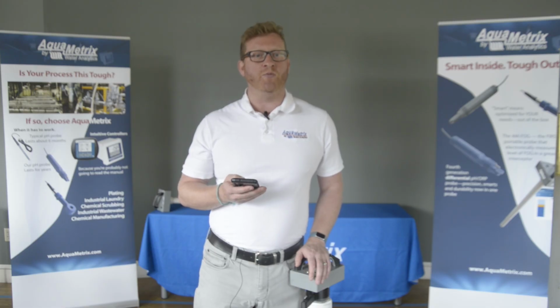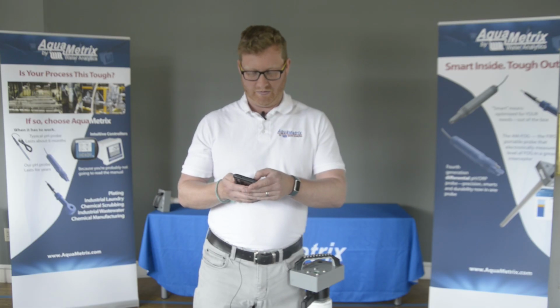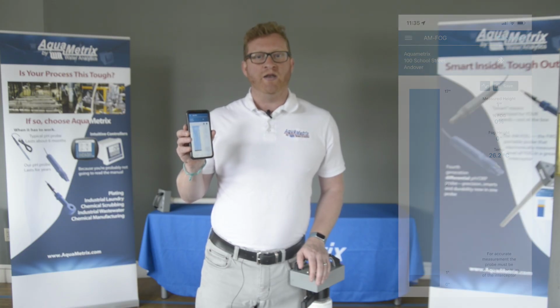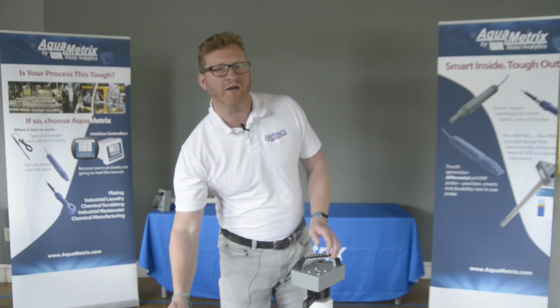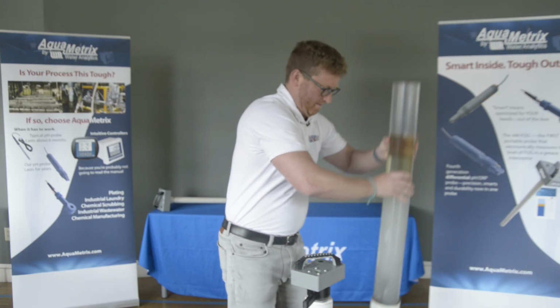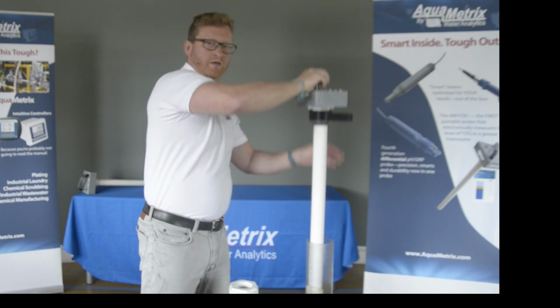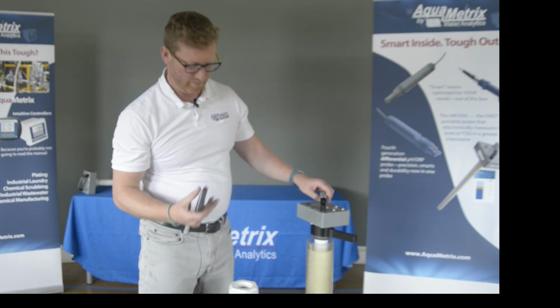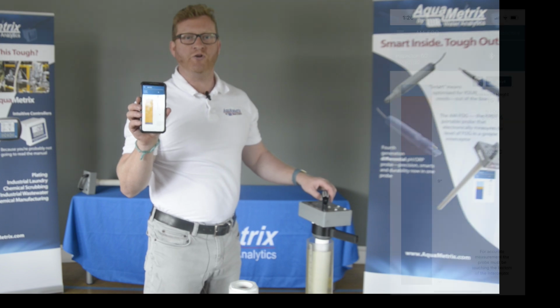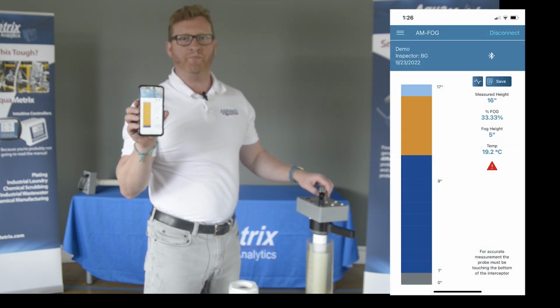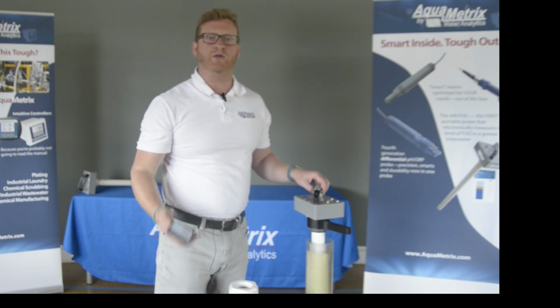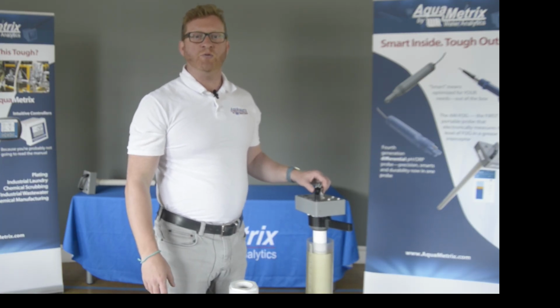Assuming I have calibrated the fog probe, I go straight to the measure screen. There I see a bar graph showing the layers of material surrounding the probe. Right now it's all light blue because light blue is the color of air. Now watch what happens when I insert the probe into a container of fog. After a few seconds, the bar graph shows blue at the bottom, yellow in the middle, and light blue on the top. Dark blue is the color coding for water, and yellow is the color for fog. Light blue is air, and the app uses this level to determine the height of the liquid in the interceptor. If sludge is enabled, it will appear as brown.